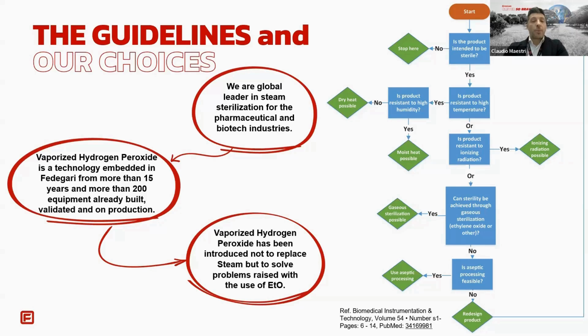So the selection of an appropriate sterilization modality is a critical step in medical device development and ensures an effective sterility assurance process. An unoptimal choice can lead to severe consequences, including inadequate sterilization, compromised device functionality, harm to patients, and costly delays in product launches and regulatory reviews. When moist heat sterilization is possible, for sure it is always the first choice. But when heat or moisture could damage the product, we need to consider low temperature alternatives. That's where hydrogen peroxide comes in.